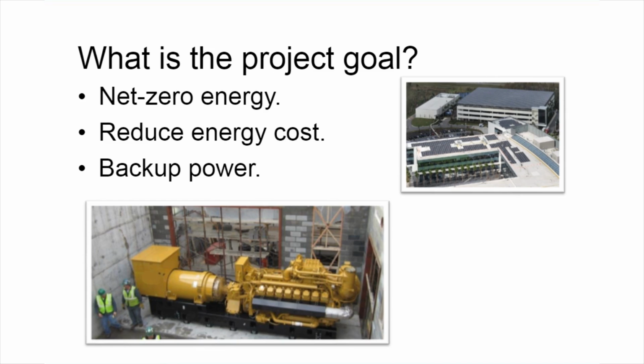So in keeping with that, you need to talk with the owner about, what is the project goal as far as energy generation equipment? Do you just want backup power meeting those minimum standards like Randy was talking about, maybe for a healthcare facility where it's going to be required for that specific building type? Or is it more that the building has net zero energy goals, or you have an owner that's really interested in looking at how they can produce their own energy to reduce their energy cost, or maybe it's in an area that the electrical grid isn't reliable, so they would rather have something to produce energy on site that then maybe they could store or offset or provide back to the grid there.